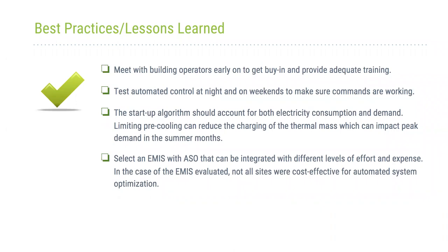Some other lessons learned: test this at night and on weekends just to make sure the commands work. The first day we tried the ML/AI based OSS, the unit didn't start. Luckily, our O&Ms are there very early in the morning and they started the unit manually. It's easier to test at night, because if your unit doesn't shut off, you'll just buy that electricity during the night—it's much easier to have a unit keep running at night than to have it fail to start in the morning.